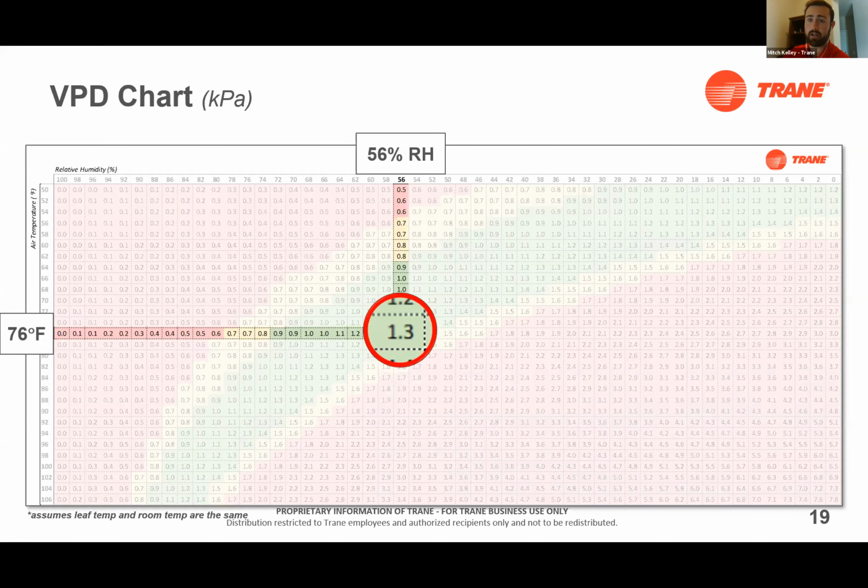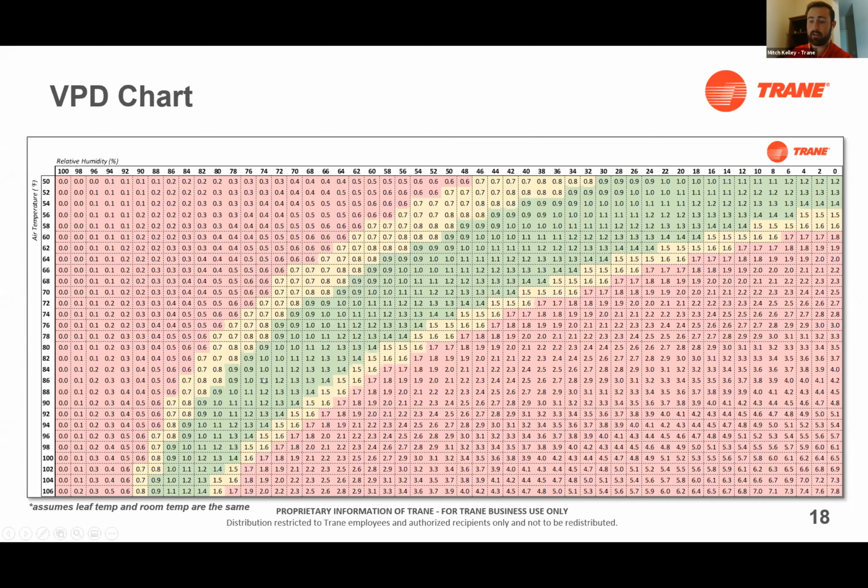Now, leaf temperature is critically important in the grow facility. So you typically want to choose a dry bulb temperature that your grow team deems acceptable. But what's important to note is if you have flexibility with your grow temperature itself, say you want it between 70 and 80 degrees, but you want to make sure your VPD is X, you can choose a point at which to design your system at a more favorable load standpoint. Something that's easier to achieve with less air conditioning and yields the same VPD as you would otherwise. A lot of times if you want a specific dry bulb temperature and specific VPD, you're going to need to spend a lot more money on your systems to achieve the same goal that you could achieve at a different point and have the same impact on the plants.